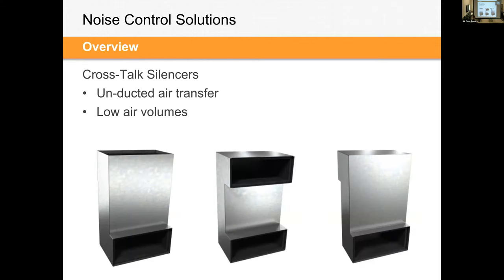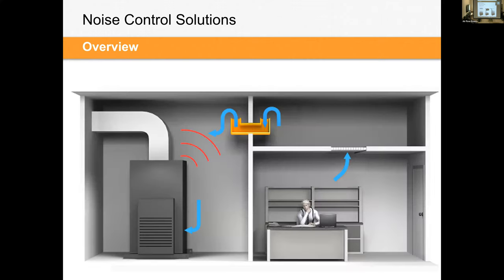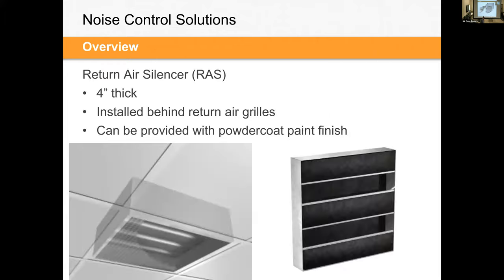Crosstalks are a great option where you need to transfer the air between two spaces without allowing the noise to also transmit through. There's typically an L, a U, and a Z shape that can be used for that intention. Something like this here. If you had a mechanical room with a common return, a crosstalk silencer would help to absorb and muffle that noise, but allow the air to still transfer installed between the partition.